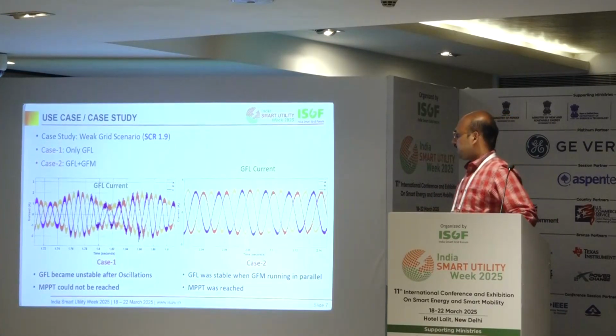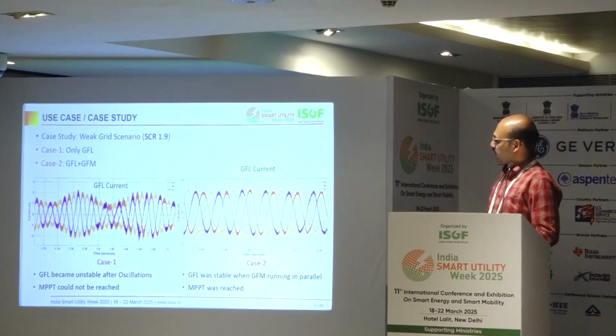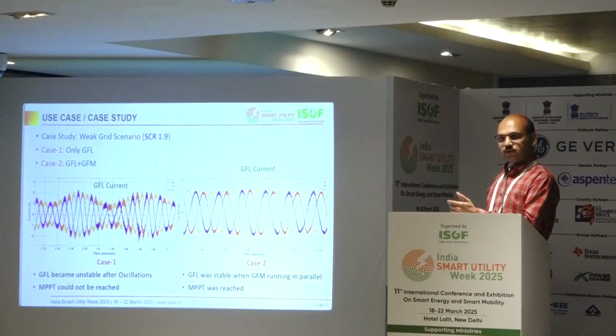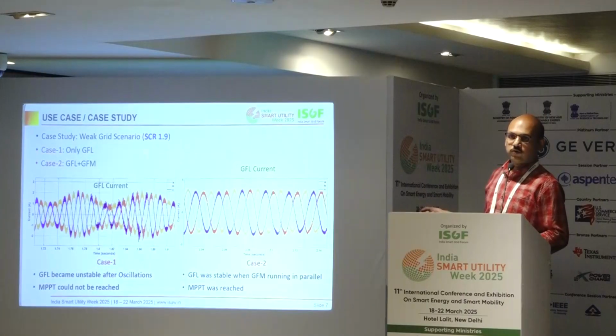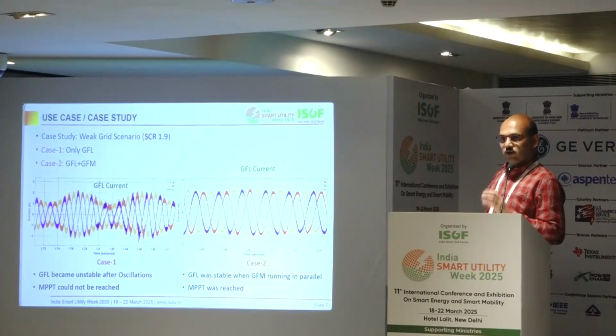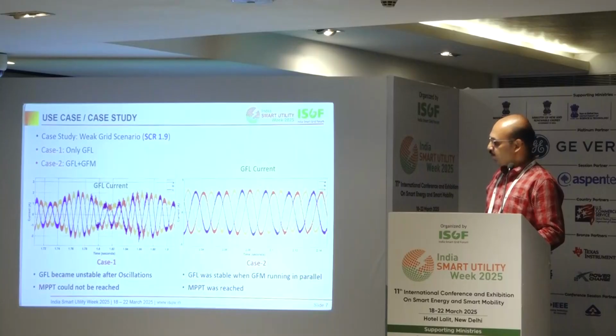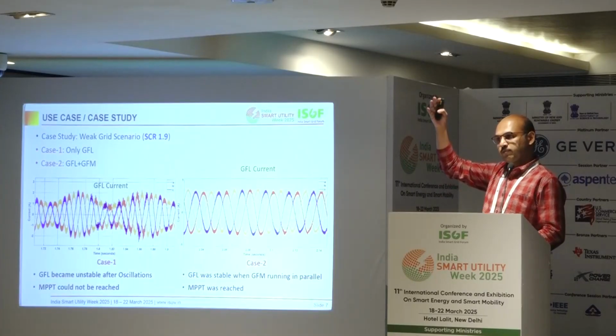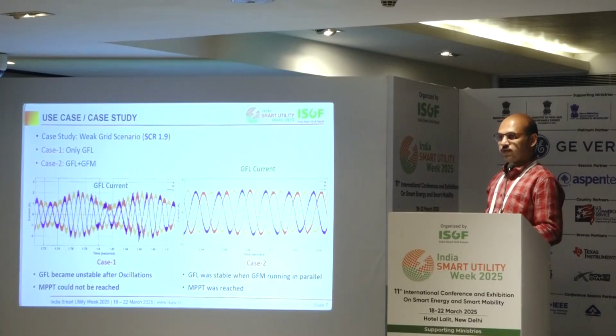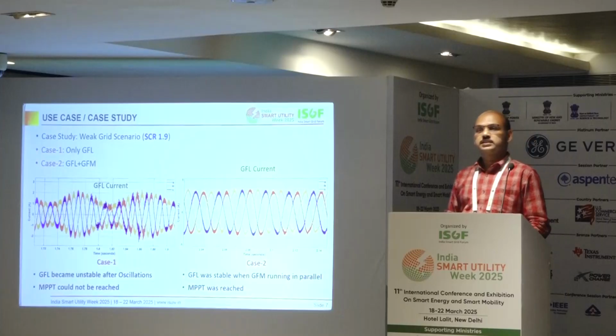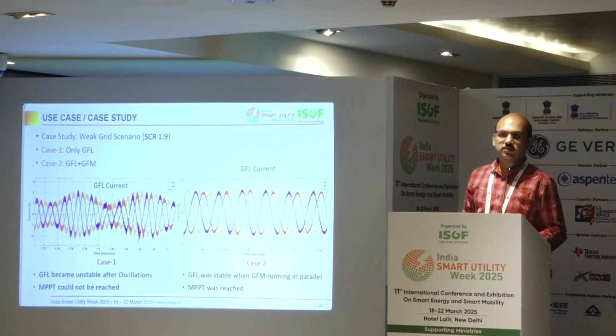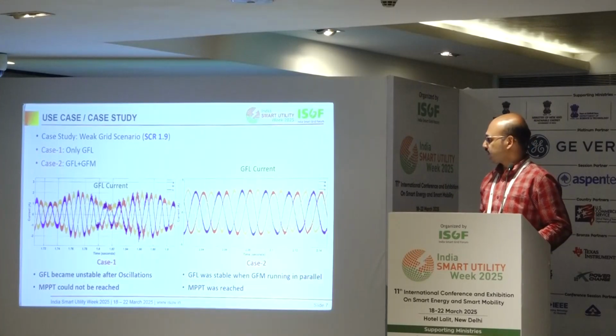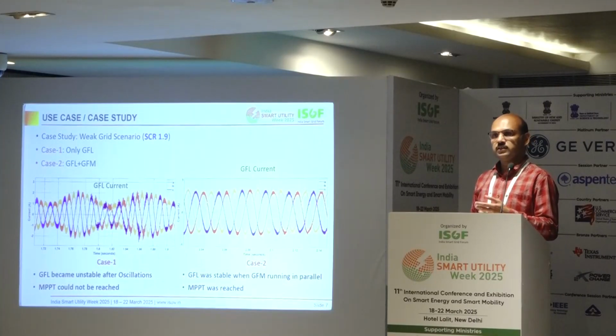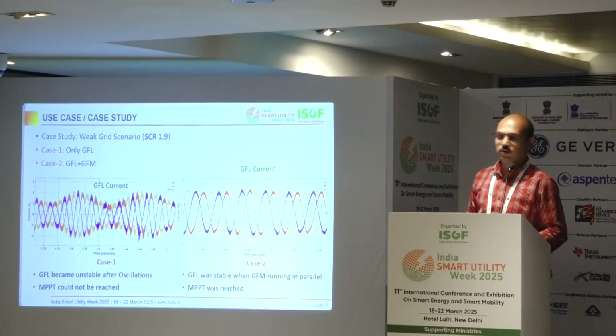What we see, a very interesting thing, in case 1, when I am trying to run only GFL at a short circuit ratio of 1.9, the current oscillates, MPPT could not reach the peak point, and the GFL collapsed. After this oscillation, the GFL actually shut down and was unable to reach the MPPT point, which is quite expected, right? In such a weak grid, it will oscillate and it will not operate.